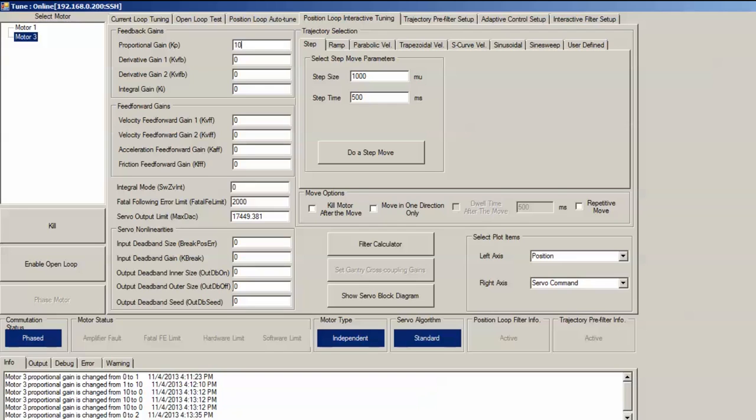And since I know this will increase the oscillations quite a bit, I'll add a derivative gain as well. Now, I know from experience that the derivative gain should be on the order between 0 and 2000, so I'll add a pretty conservative value of 250, just to prevent the motor from oscillating completely out of control and damaging something.